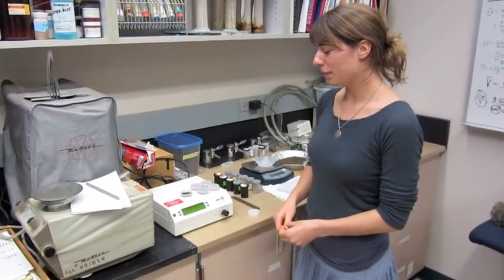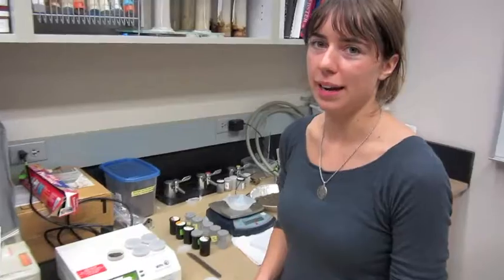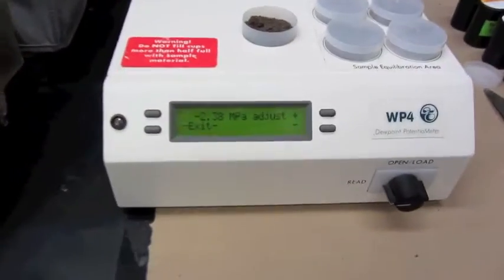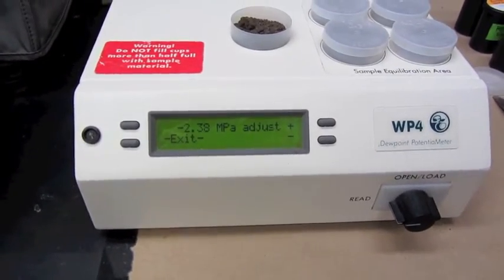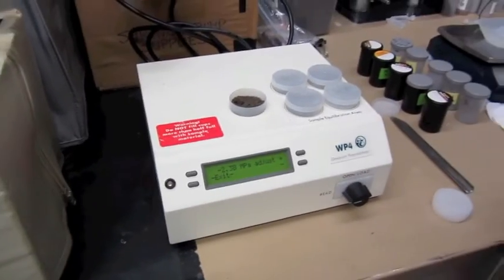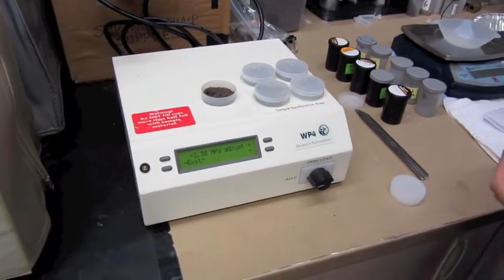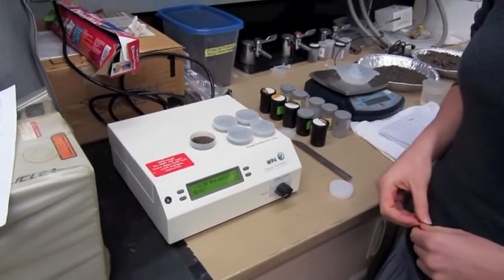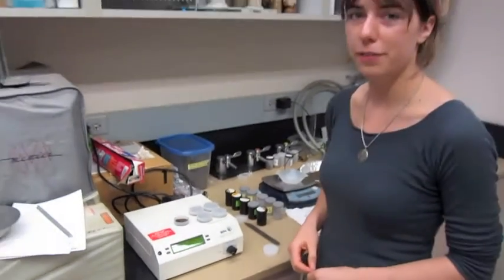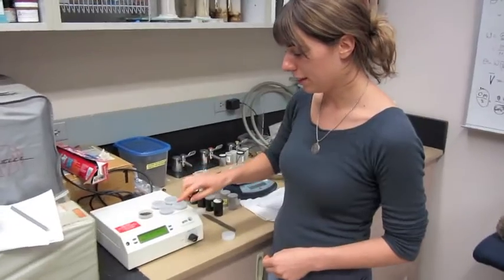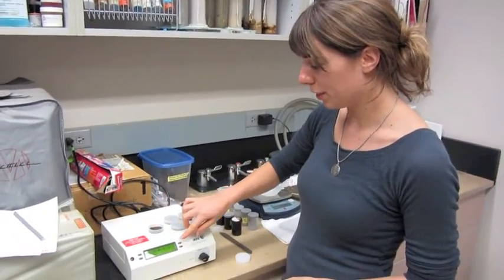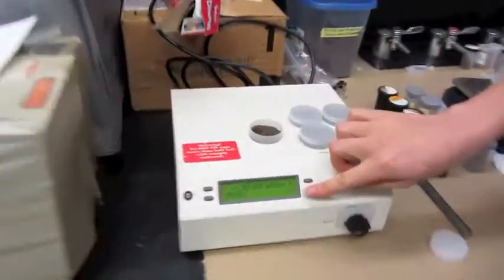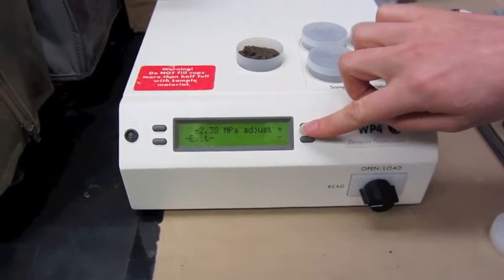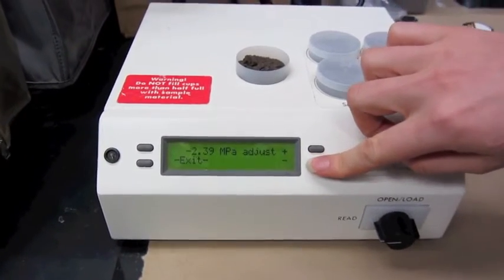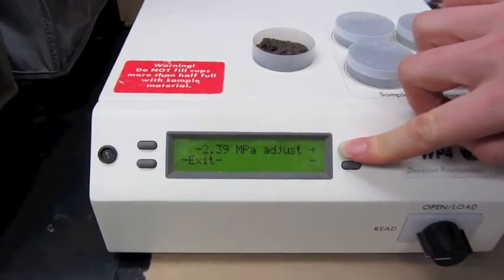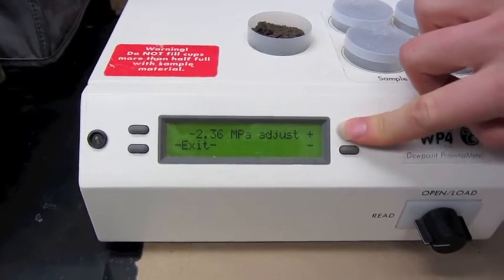Wait until the machine beeps before changing calibration. The readings should be within negative 2.19 to 2.22 megapascals, and if they are not, the first thing you should do is try cleaning the sensor, because the sensor chamber can get dirty. But if that doesn't work and they're still off, you can change the pressure by using this plus and minus button to adjust. So it's too high, so I'll bring it back down. Nope. It's too low actually, because it's a tension. So I'll bring it up.